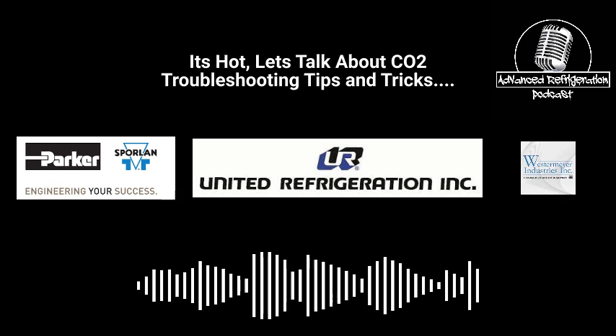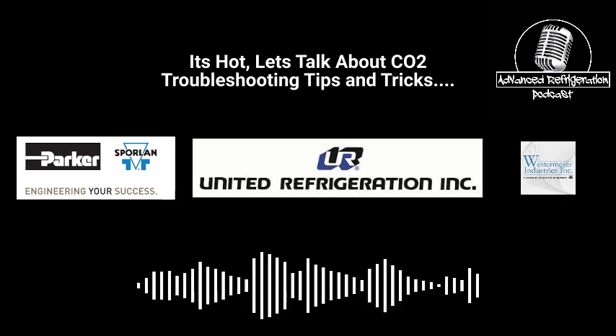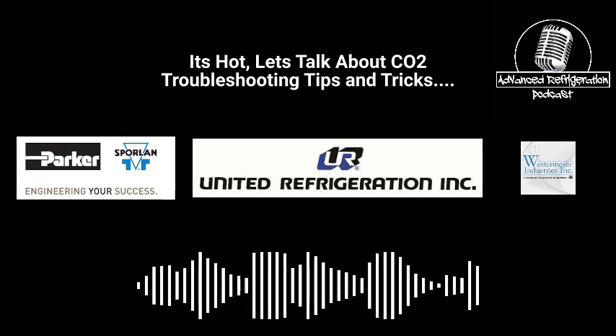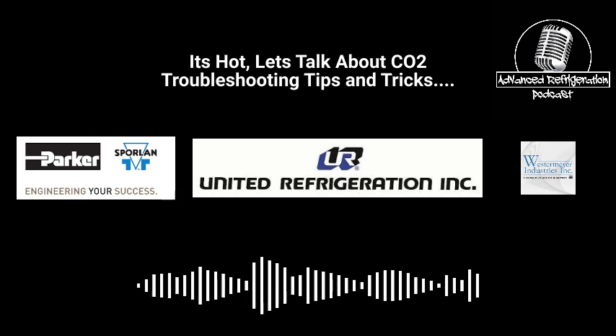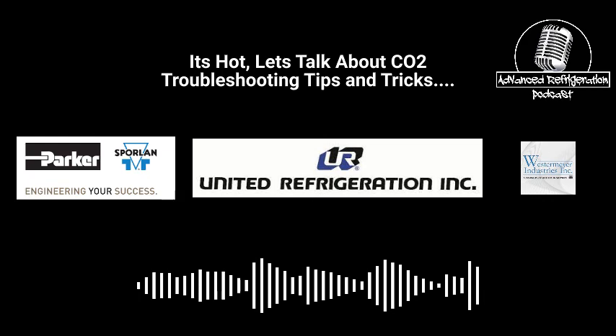Zero Zone's the only one with a big enough valve that I've seen that has actually been able to load it up. I don't know what the port is on the valve, but it's big. I know like the Hill Racks, it's like a DN2, which is tiny. So going up to a DN4, I remember we were discussing this online one day, we drilled one out to what would be the orifice of a DN4, and it worked phenomenal.